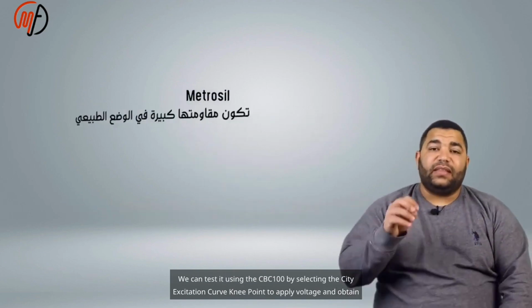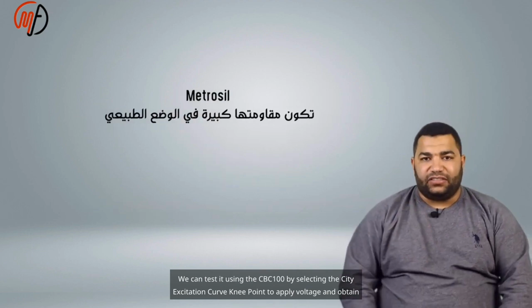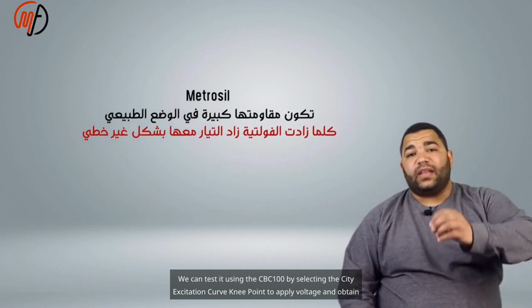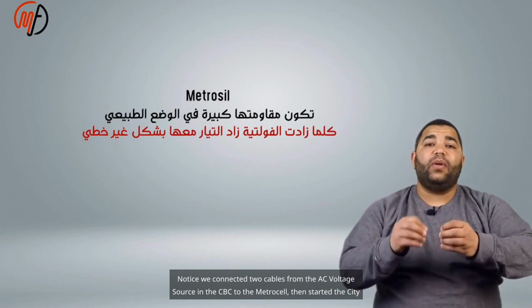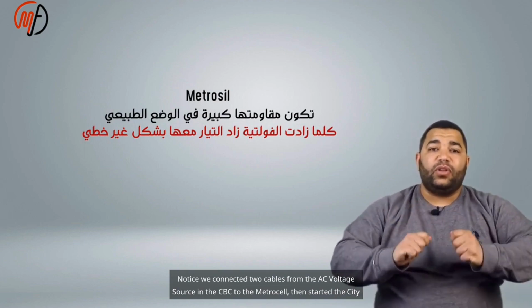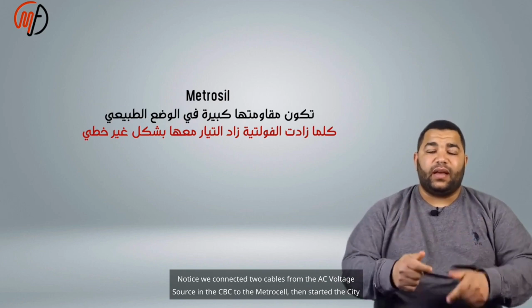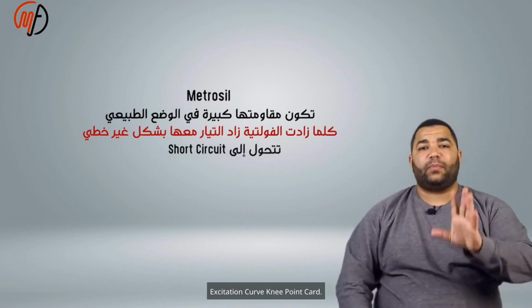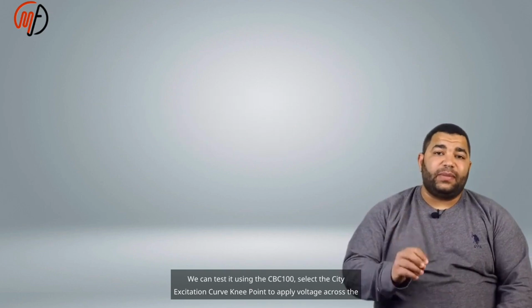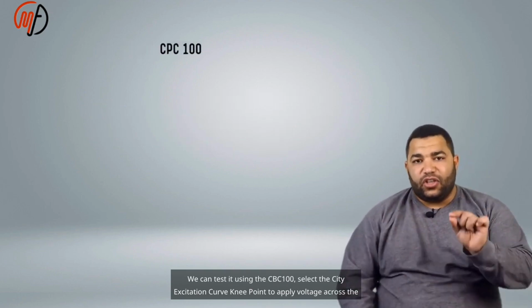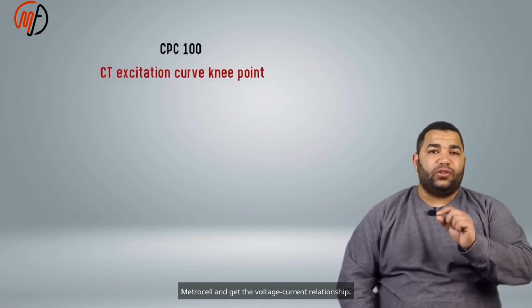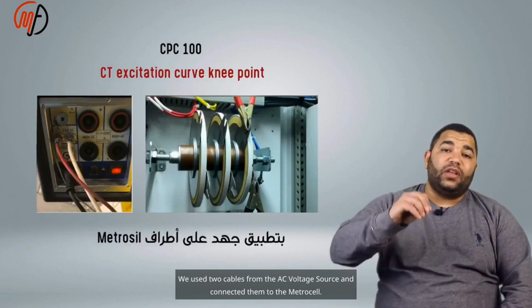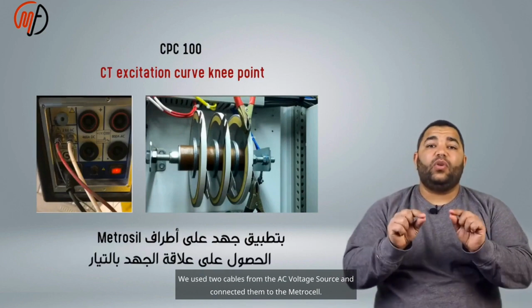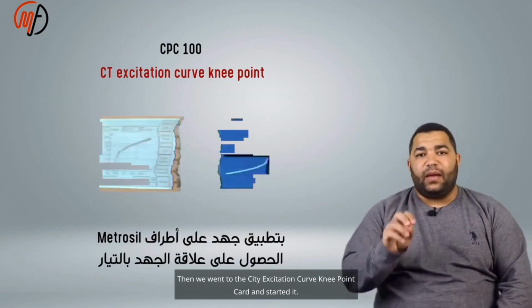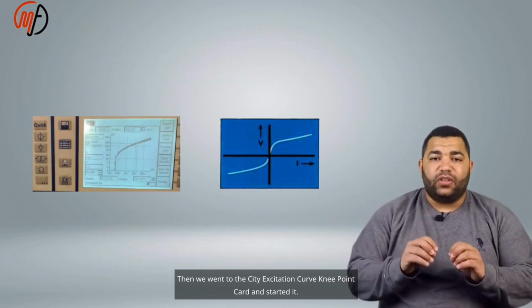We can test it using the CPC 100 by selecting the excitation curve knee point card to apply voltage across the Metrosil and obtain the voltage-current relationship. Notice we connected two cables from the AC voltage source in the CPC to the Metrosil, then went to the excitation curve knee point card and started it.